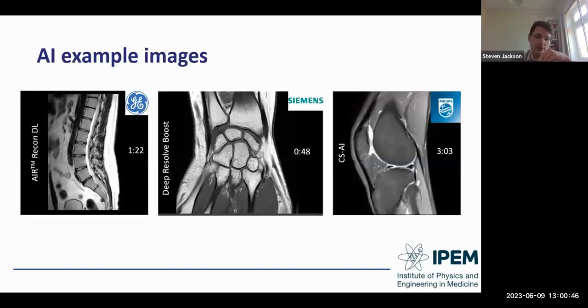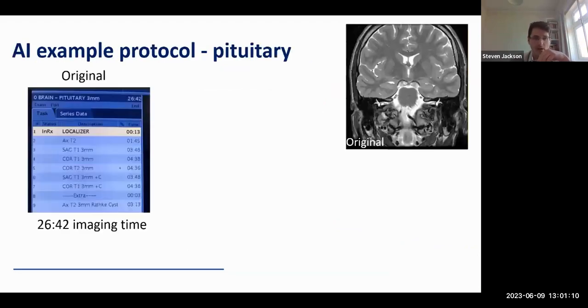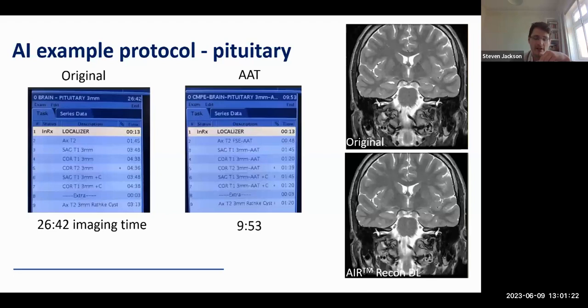Example AI images: Air Recon DL on a lumbar spine acquired in under a minute and a half. In the middle, a wrist scan with DeepResolve Boost technology in under a minute. For Philips CSAI, an original scan of four and a half minutes was reduced to three minutes. Very impressive time savings with very good image quality. An example protocol: a pituitary protocol at a local centre in Greater Manchester was originally 26 minutes 42 seconds. Following AAT implementation, it came down to just under 10 minutes.